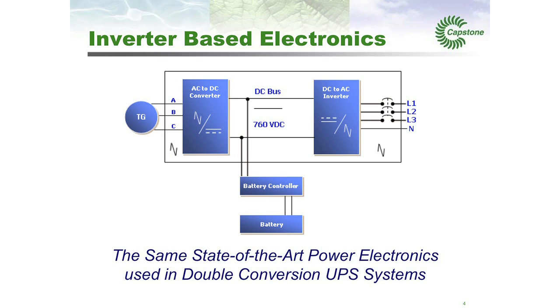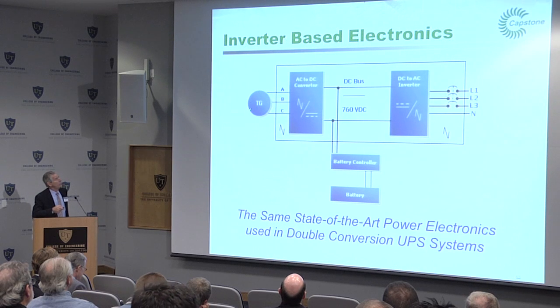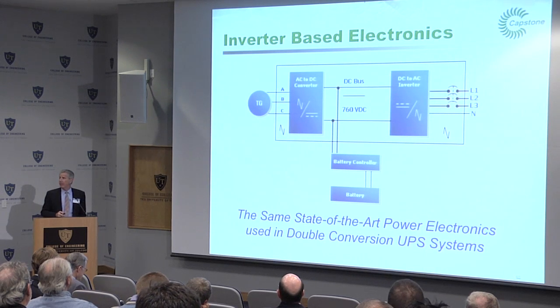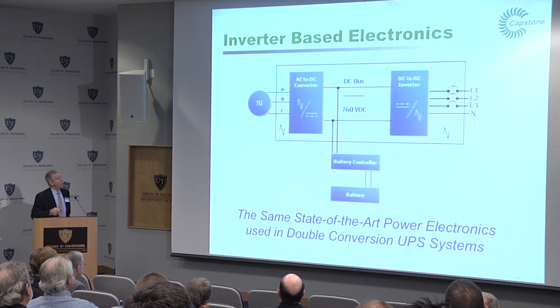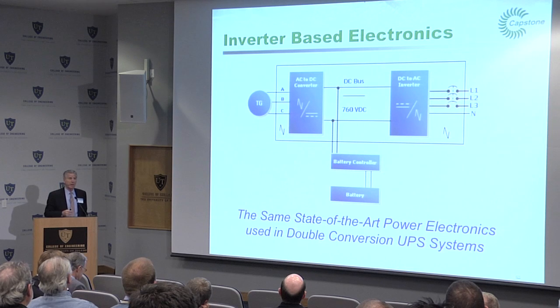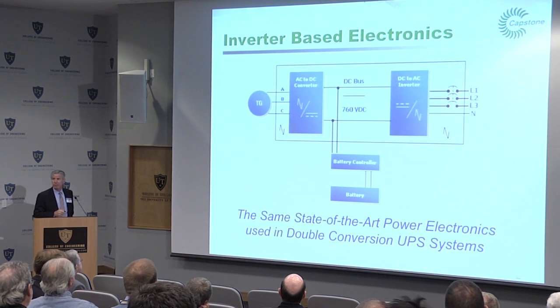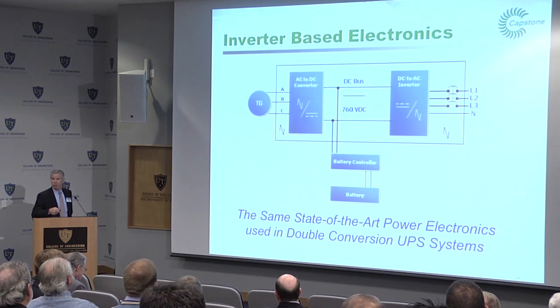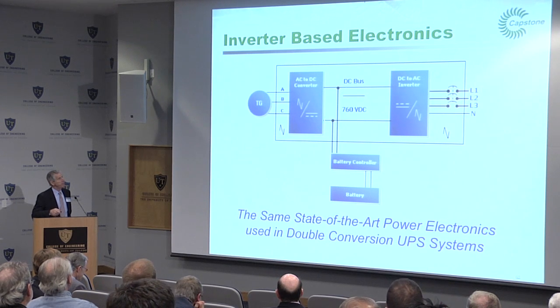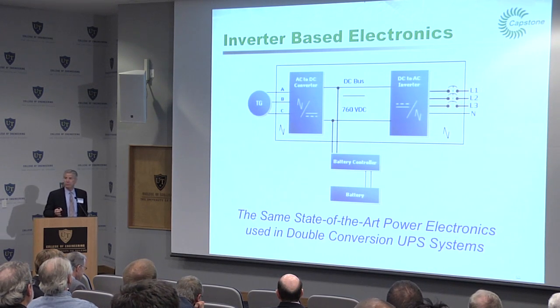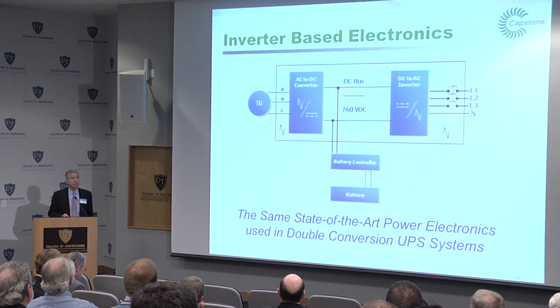So what we do is take advantage of state-of-the-art power electronics, the same kind used in a UPS system today or a variable frequency drive. We take that high frequency AC coming out of the turbo generator assembly and rectify it to DC, giving us an internal DC bus converting the high power, high frequency to DC. Then to connect to the grid, we have another module, an inverter, using the same kinds of power electronics, to take the DC and convert it to 50 hertz or 60 hertz AC for use in the facility.